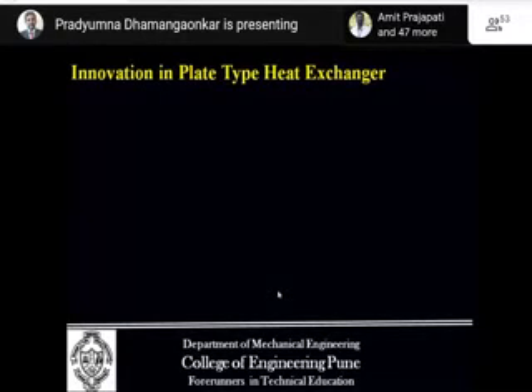What is the innovation in the plate type heat exchanger? The problem with the plate type heat exchanger is that as it is made up of metal, it is very bulky. Its weight is very, very high. So hence there is a necessity to go for reduction of weight. There is one more problem: as the weight is higher, the thermal inertia is higher. The thermal inertia means the time taken by that material to reach a certain temperature.